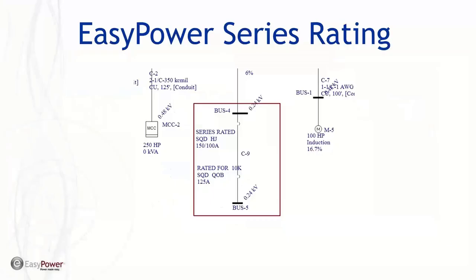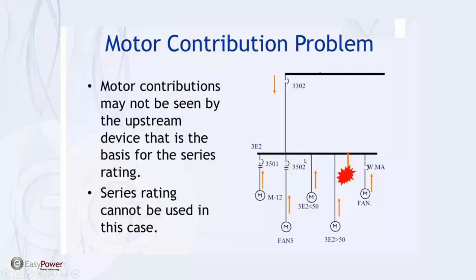With the 100,000-amp rating, going back to short circuit and faulting the bus, we see equipment duty is no longer a problem. However, there's an important caveat: when we have motor contribution, the fault on a feeder will see current not only through the main breaker but also contribution from other motors. In that case, its exposure will be more than limited by the upstream breaker, so series rating cannot be used.